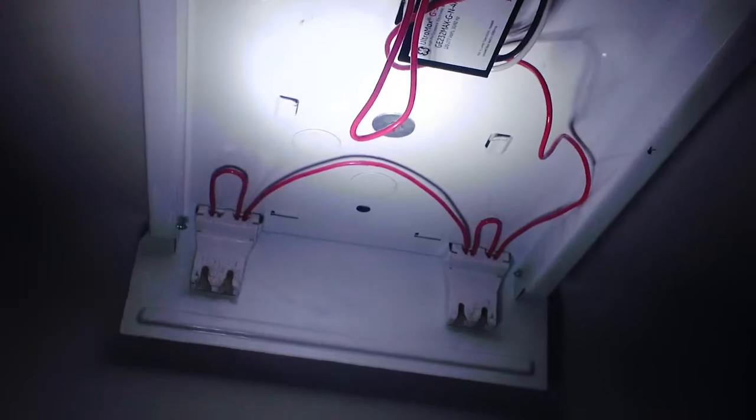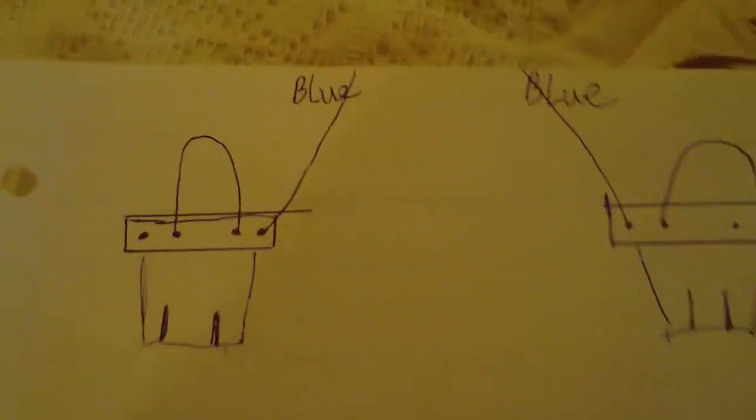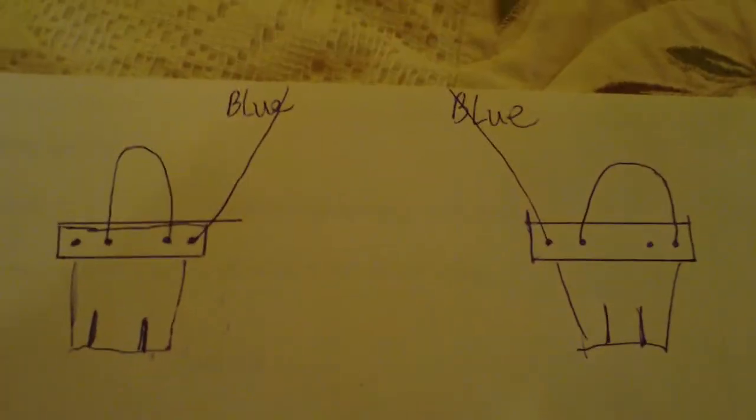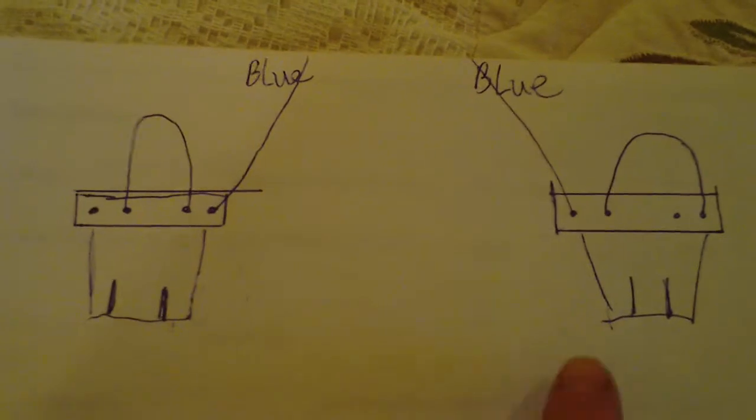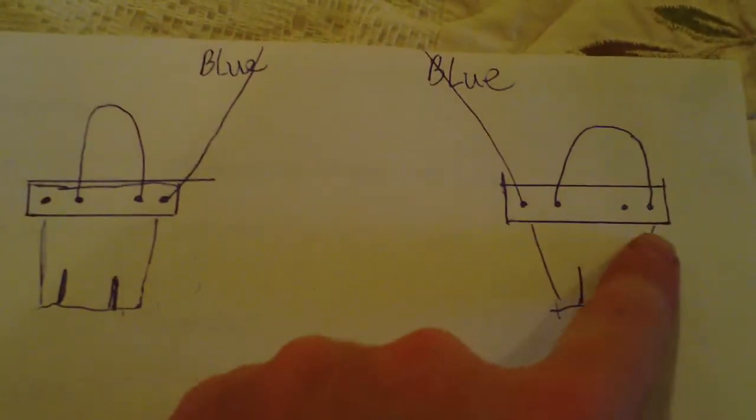And then the hardest thing really is getting the wires out of those tombstones. You just got to twist the wire. Grab it firm and twist the wire and the tombstone. Otherwise, don't just yank and start pulling. You got to twist and they'll come out easy. So there's your blue wires feeding from the ballast coming in and just make a jumper wire over to the other side.